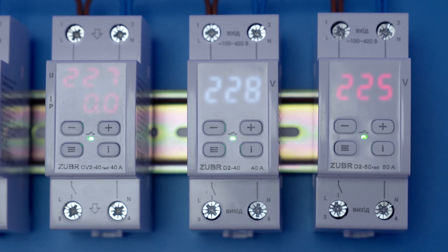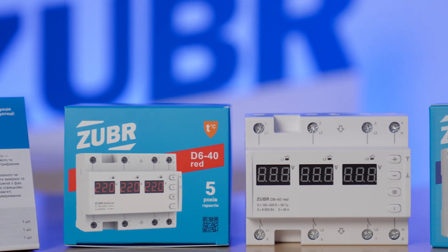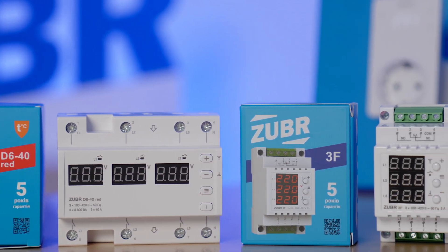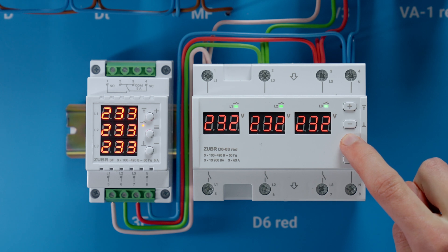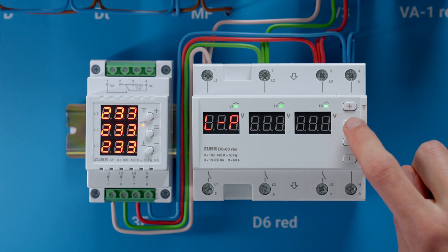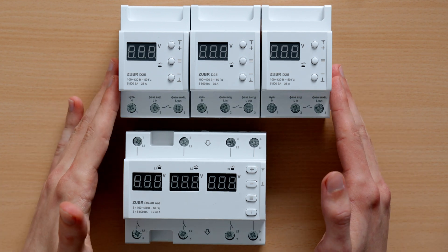Be sure to check out our website for more specific info on the models — the link is in the description. Next category: three-phase voltage relays, D6 and 3F. Apart from high and low voltage spikes, these relays also protect from asymmetries and phase breaks, and control the order of phase alternation. There are 40, 50, and 63 ampere models for the D6 relay. Its main feature is that it can function in both one-phase and three-phase load modes, so instead of using three separate relays, you can use one D6 model and still change values separately for each phase — saving cost and space.